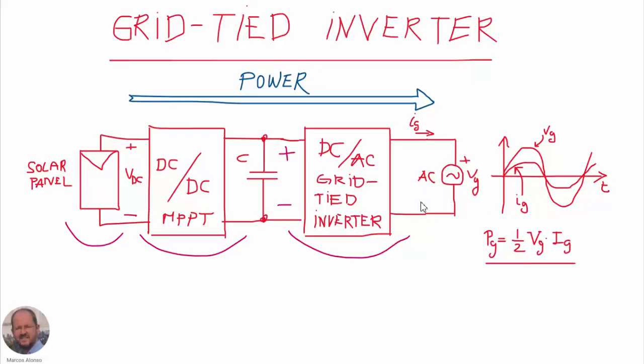We want to inject into the network a current waveform that is going to be in phase with the grid voltage. The power goes from the solar panel into the grid such that we have a power factor almost equal to one. Therefore, the power we inject into the grid follows the expression: one-half times the peak voltage of the grid times the peak current we are injecting. The main objective of our grid-tied inverter is to generate this current in phase with the voltage.